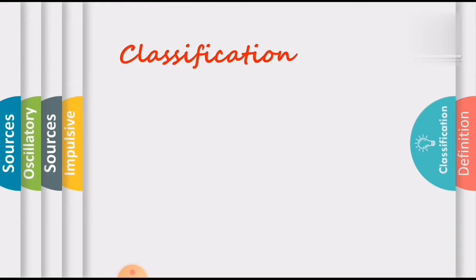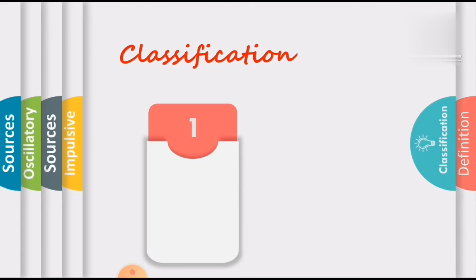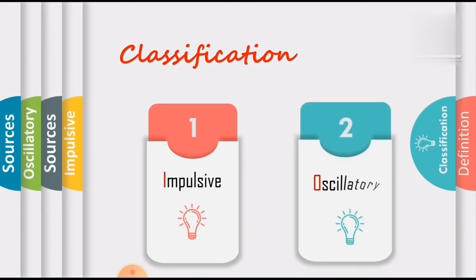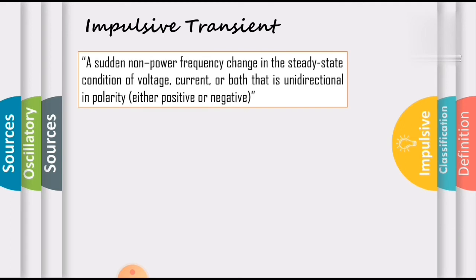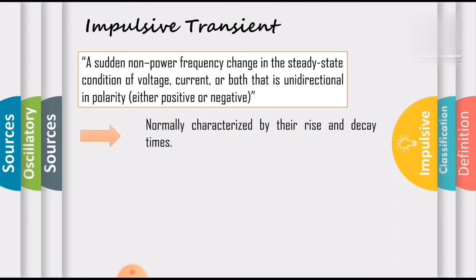These transients are classified into two types: one is impulsive, and the second one is oscillatory. According to the definition, an impulsive transient is a sudden non-power frequency change in the steady state condition of voltage, current, or both, that is unidirectional in polarity — that is, either positive or negative.